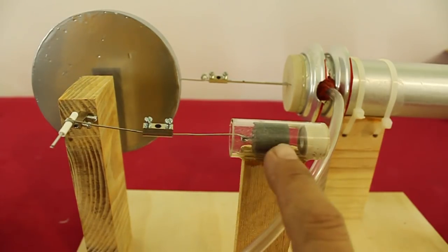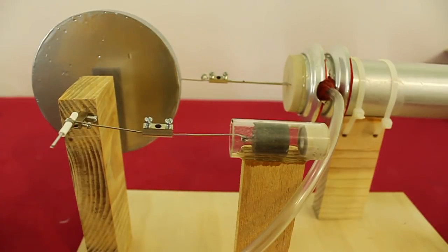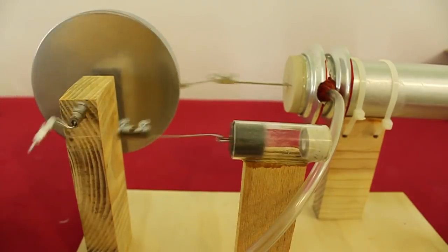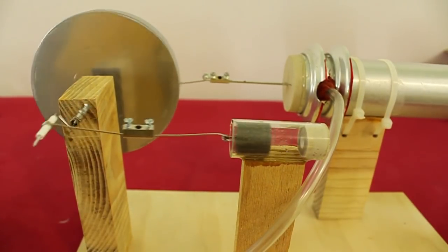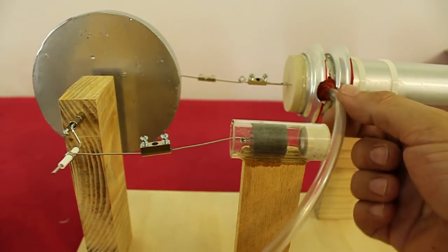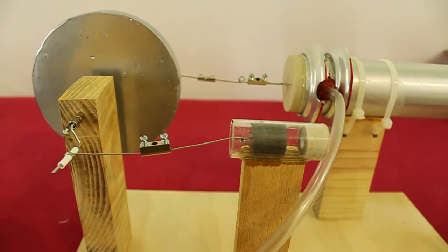The piston has a good seal which we can verify by blocking the air intake. So it only remains to connect the hose that comes from the displacer piston.